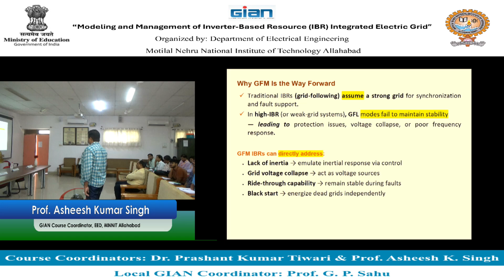Core capabilities of grid forming IBRs: they have the feature of voltage source behavior. They provide controlled magnitude and phase, and that enables grid forming. Virtual inertia they can provide to stabilize frequency and lower the rate of change of frequency. Means once you are adding the inertia synthetically, the rate of change of frequency is going to come down. Black start capability, reactive support during faults. This reactive support is going to support the voltage, so voltage drop can be taken care of, right, and contribute to system strength. Harmonic and unbalanced mitigation they can do, right.